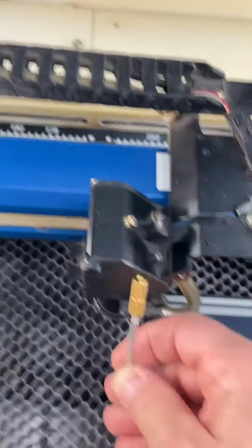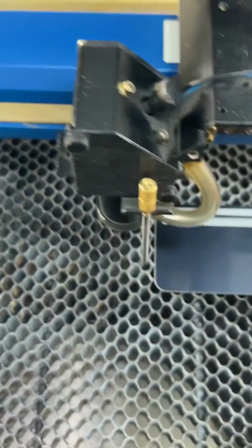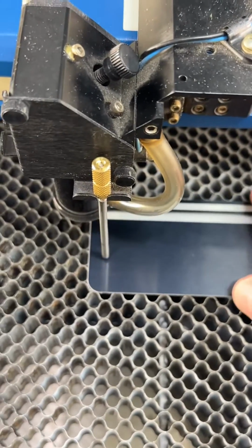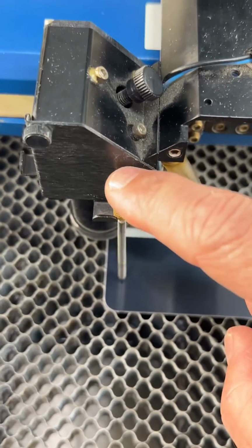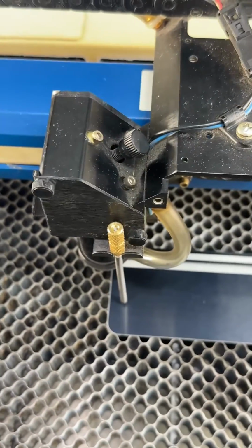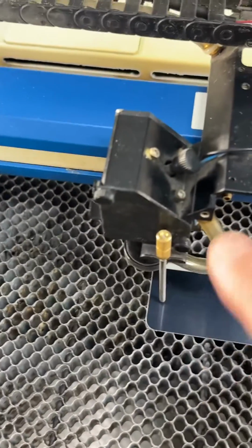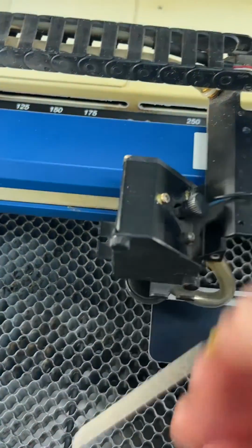Then we're going to use our manual focus gauge. And this should just barely touch the material. And it does. So once our manual focus gauge just barely touches, then we know our gauge is set correctly. So that's good. Then we're going to go ahead and push done.